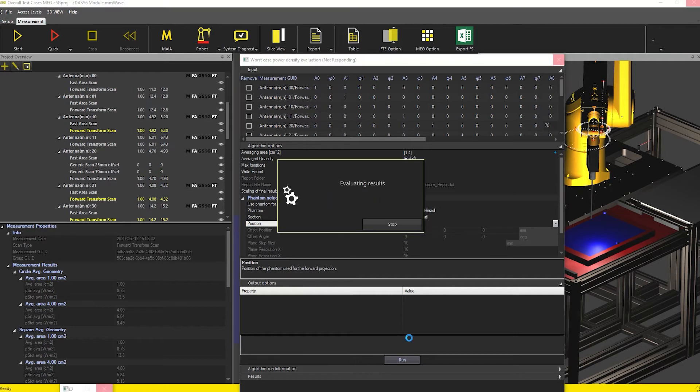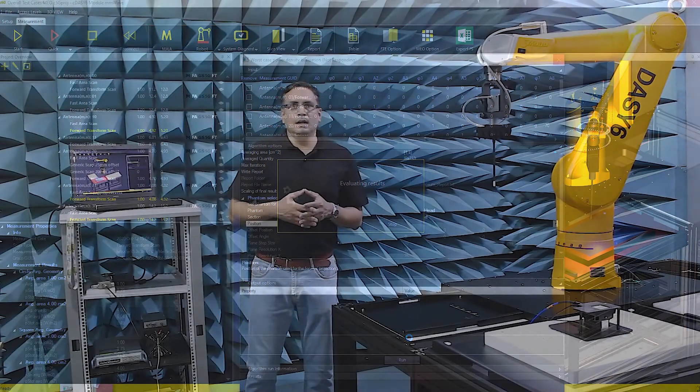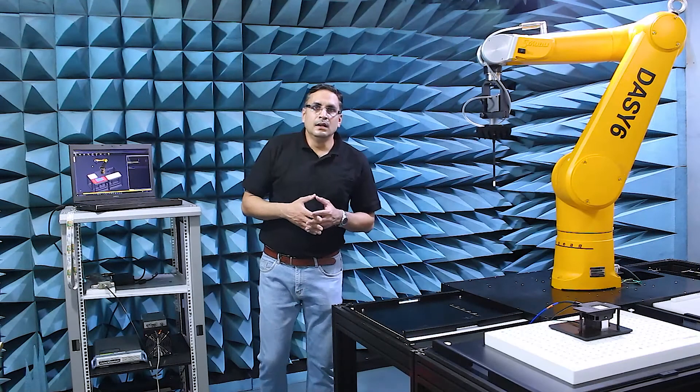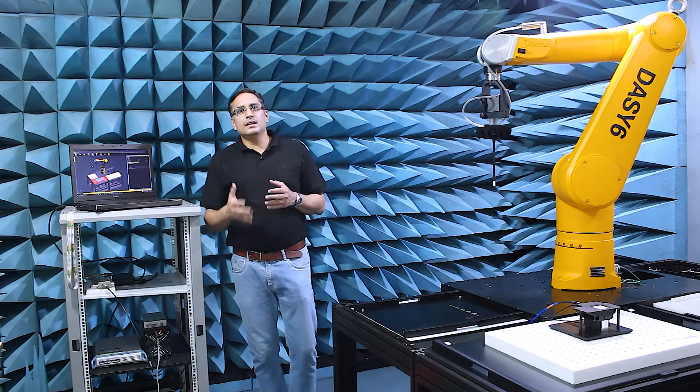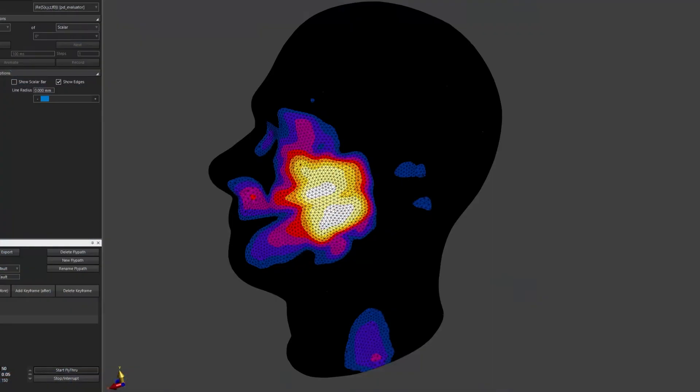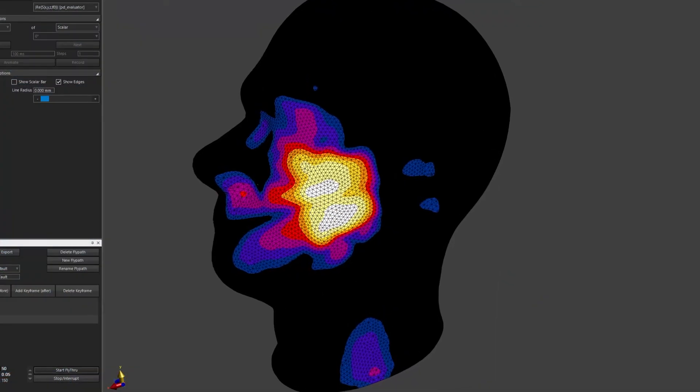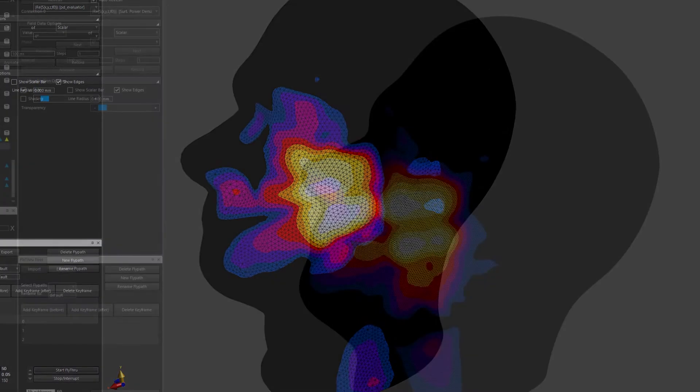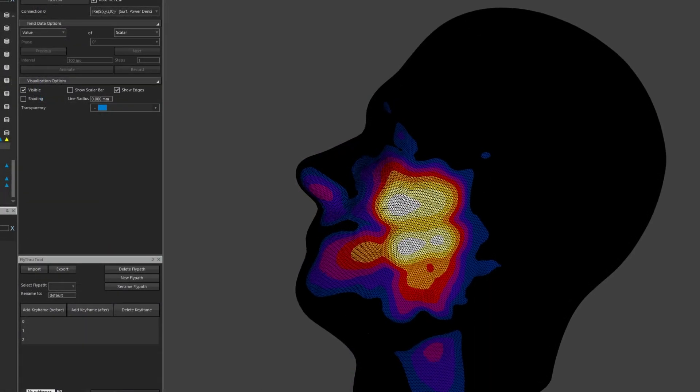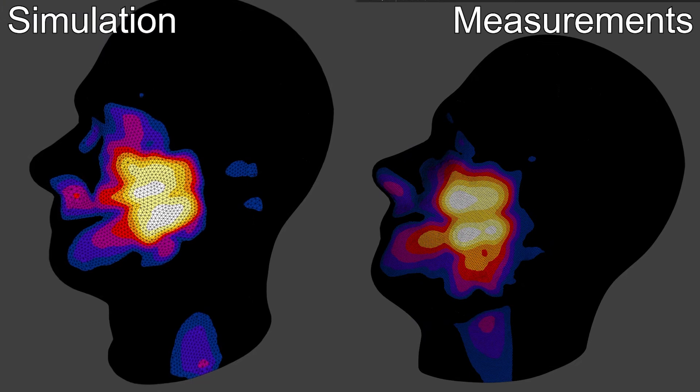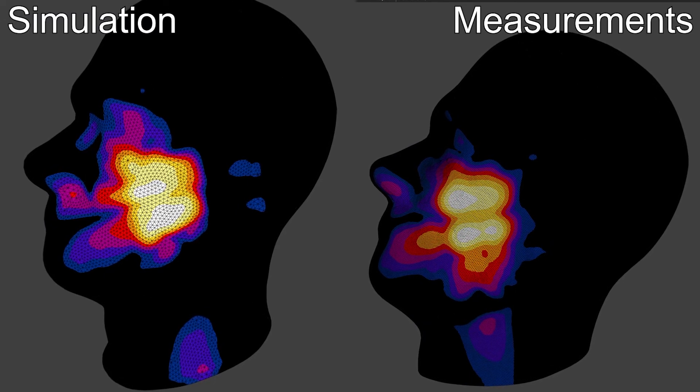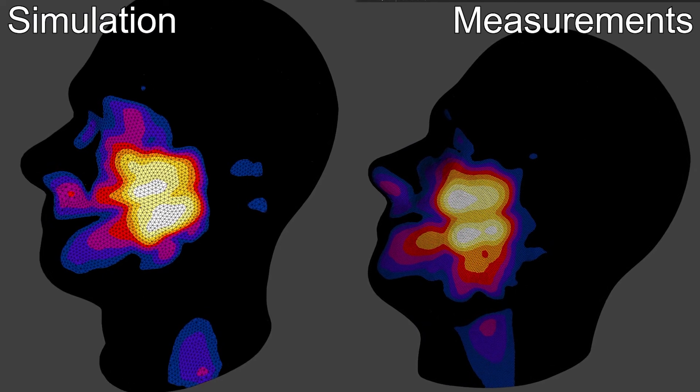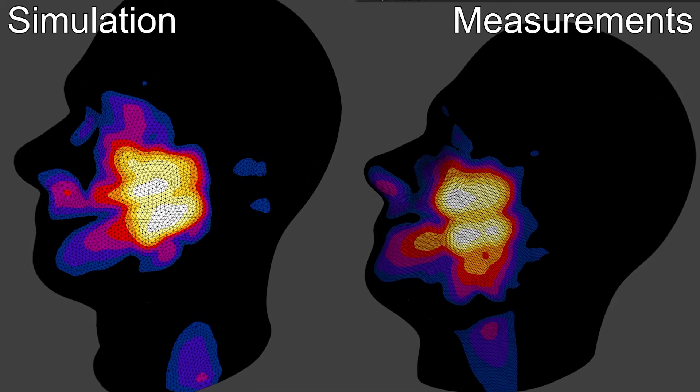The optimizer evaluates the measured data and finds the phase or amplitude combination giving the worst case power density on the SAM right head and flat phantoms. Indeed, simulation and measurement results in the same worst case configuration with a deviation of only 1 dB. This is very good considering that the validation device has not been fully calibrated yet.